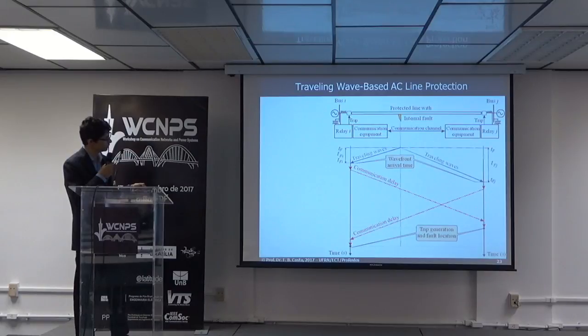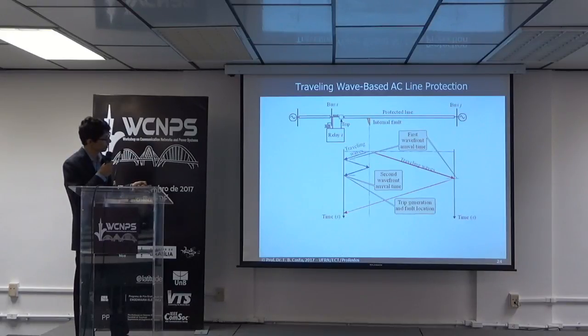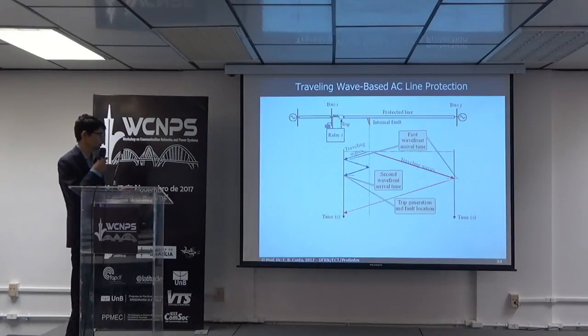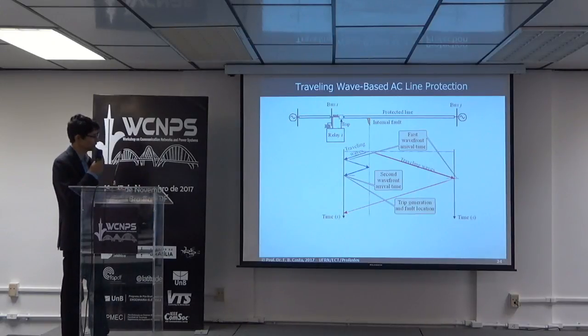However, there are other possibilities. A traveling wave-based protection by using just information from the single line, from the single terminal. Here, it's necessary to detect the beginning of the fault as well as to detect the reflection from the fault point. By detecting both pieces of time information, it's possible to locate the fault, identify that the fault is on the protected line and perform the protection of the line.